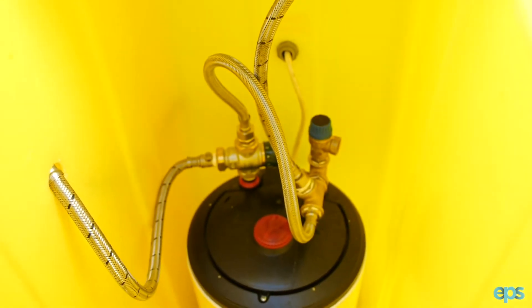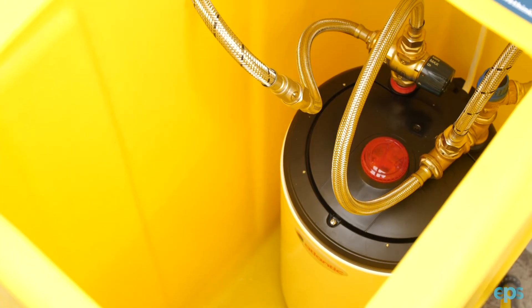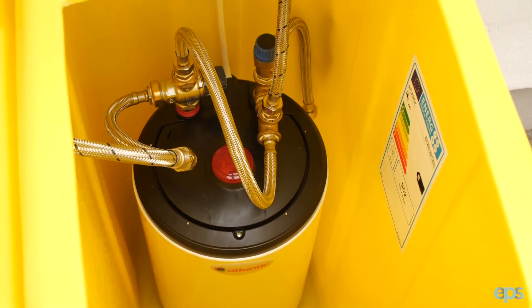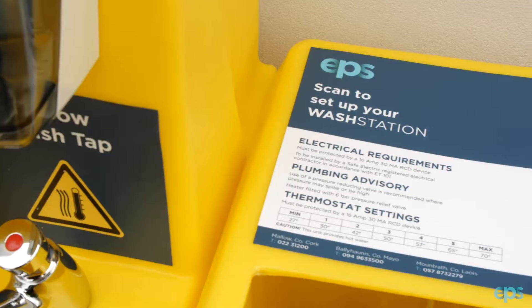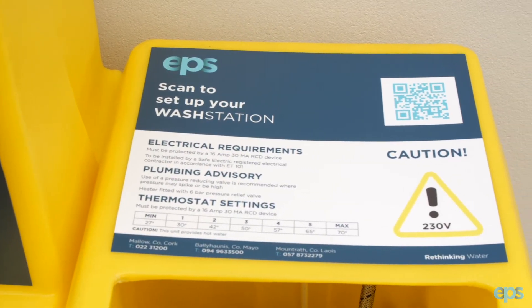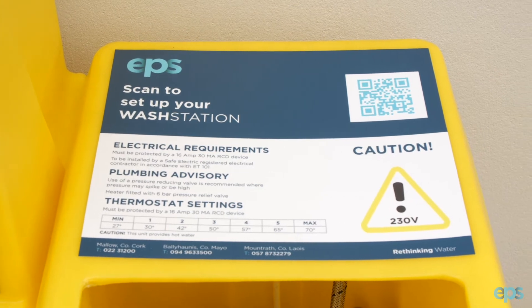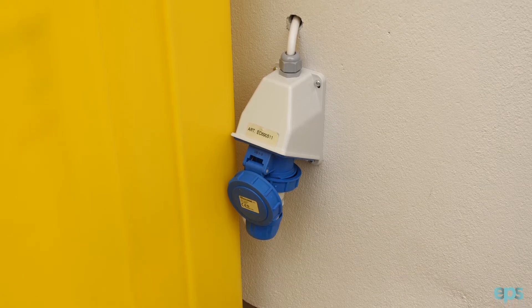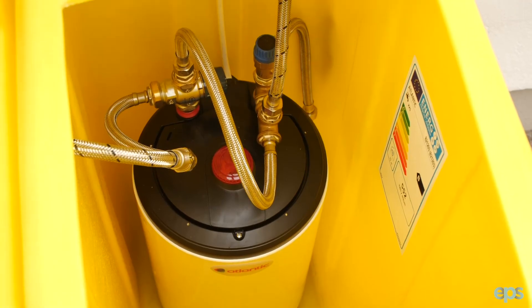When installing the wash station it is very important that all electrical requirements, plumbing advice, and also the thermostat settings are adhered to. With electrical requirements, the unit must be protected with a 16 amp 30 milliamp RCD device. This is to be installed by a Safe Electric registered contractor in accordance with ET 101.